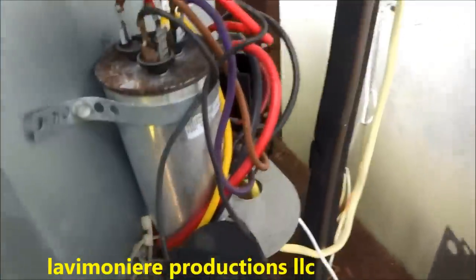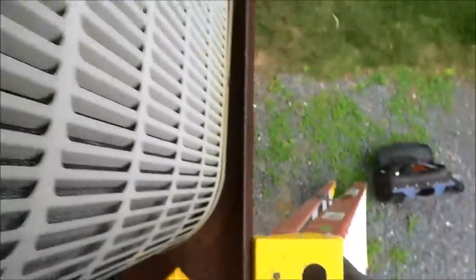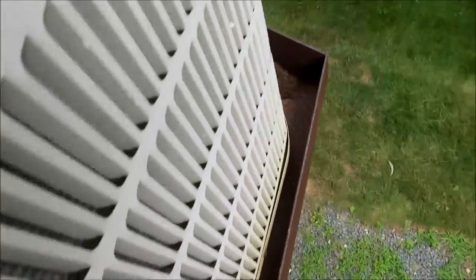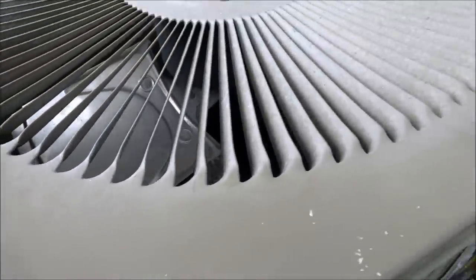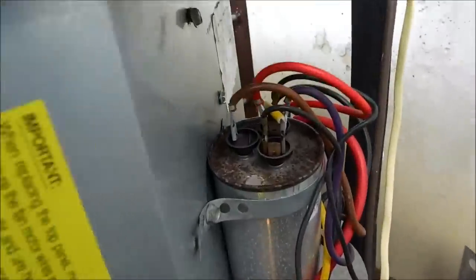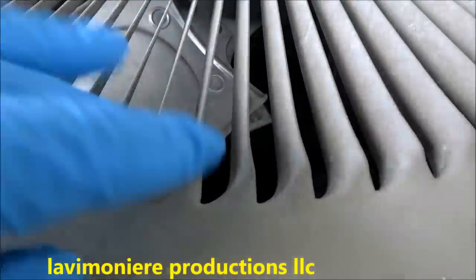So it's probably a bad capacitor. The compressor did start before, it's just that the fan's not spinning. He's going to shut the power off for us so we're going to check it. Look at this - no disconnects. Up here on a flipping platform from hell. I'm thinking it's a bad capacitor, or a bad fan, because the compressor did kick over a couple of times.